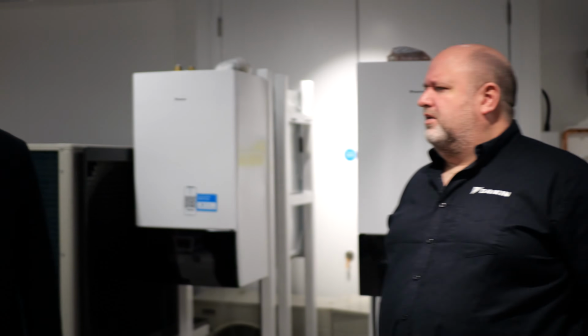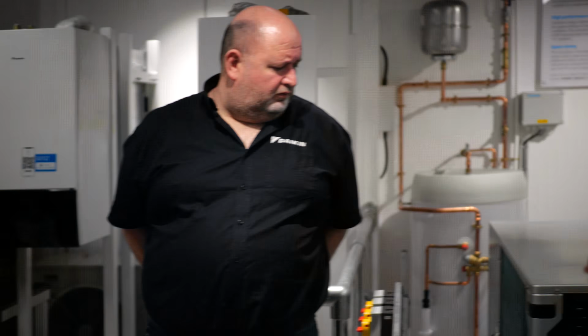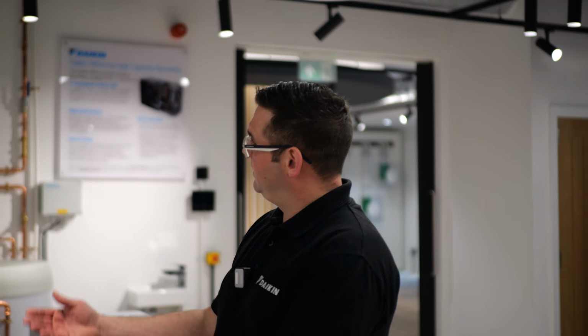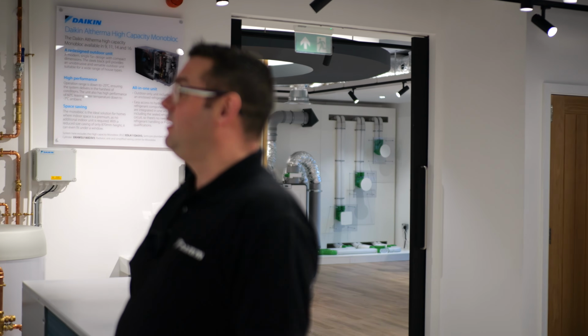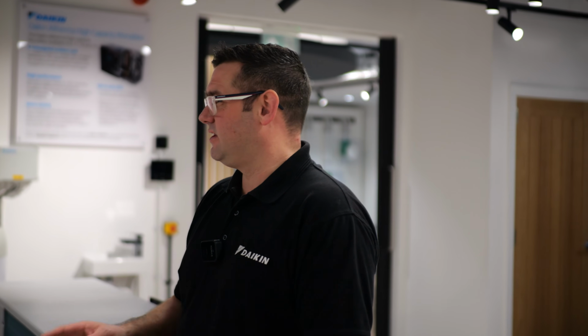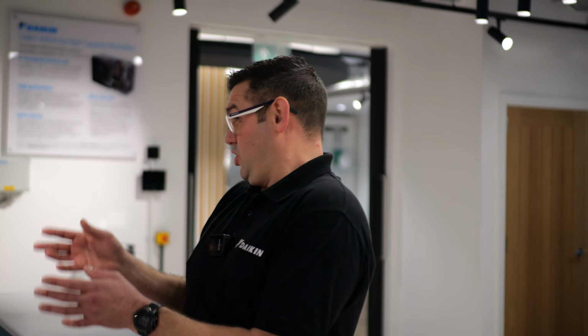Right. Because I know with all the grants previously, you wouldn't get a sign off on your grants unless your design could demonstrate 55 or below. Which is why, in the first instance with the HT, you struggled to get the grant on the original HT unit, because it would achieve a higher flow temperature, and they were like, well, hang on a minute, what's your design? So there was a time when you could have got an HT, but you had to supply design information that could demonstrate that you could still heat your property with a flow of 55 or below.